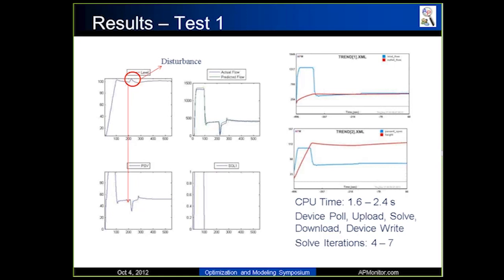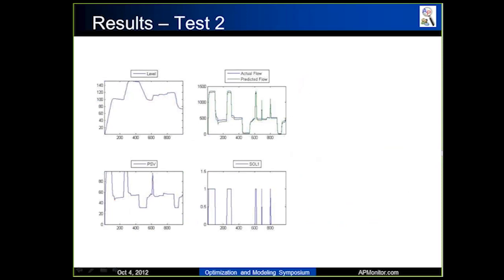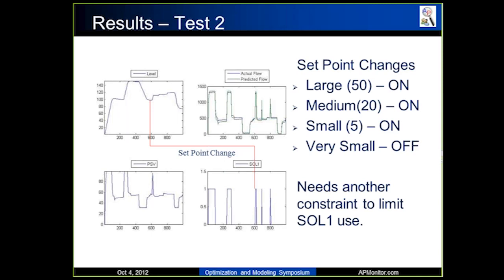The next slide gets a little more interesting. On this slide, what I did is I changed setpoint. So from here, I changed the setpoint from 100 to 150, and what you'll see is it turns back on the solenoid valve again, just like it was as you would expect. And then once it reaches the setpoint right up here, it of course turns it off again. And then you can see more setpoint changes here as well, and it does very similar things.